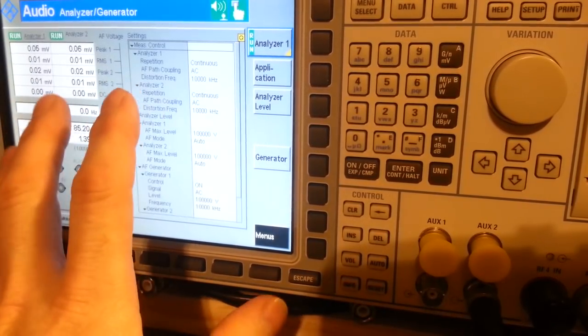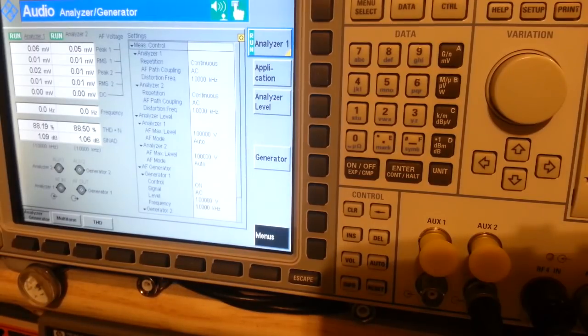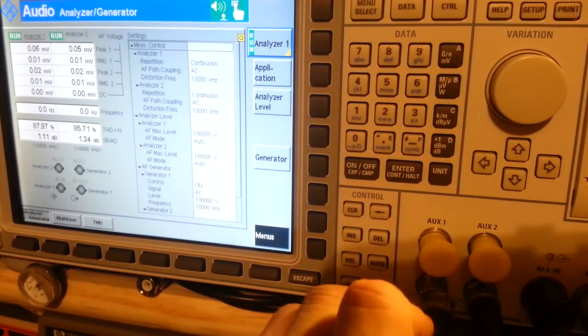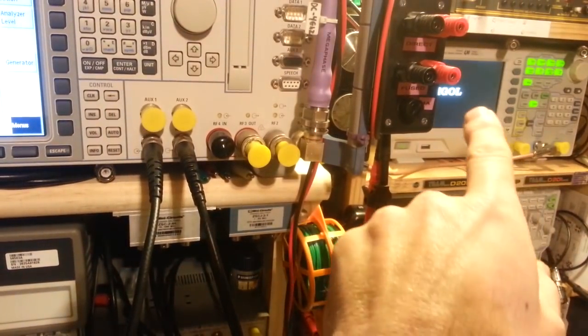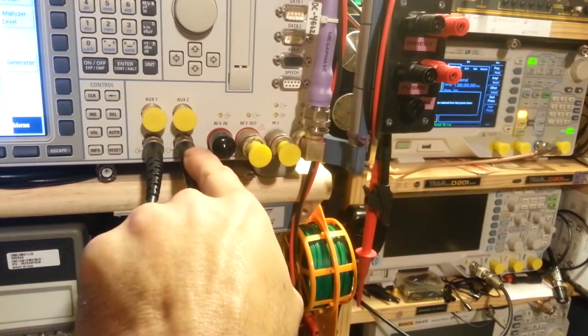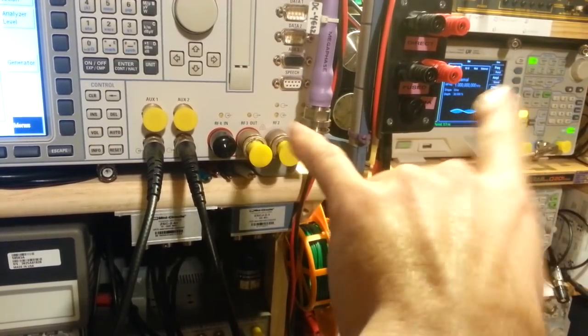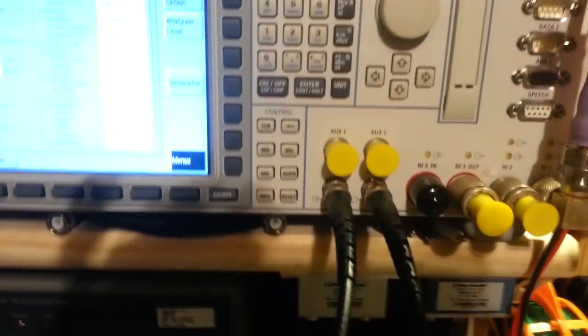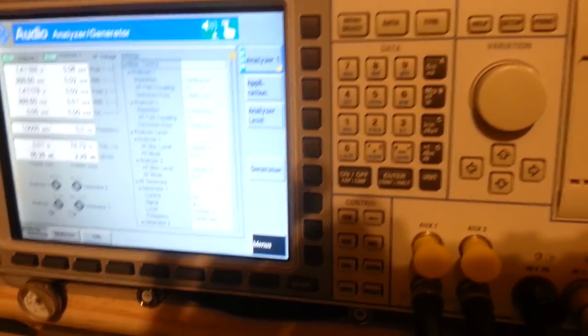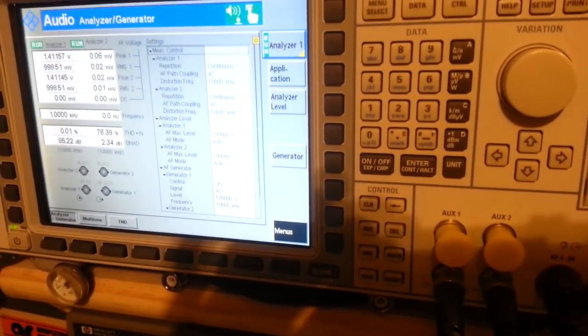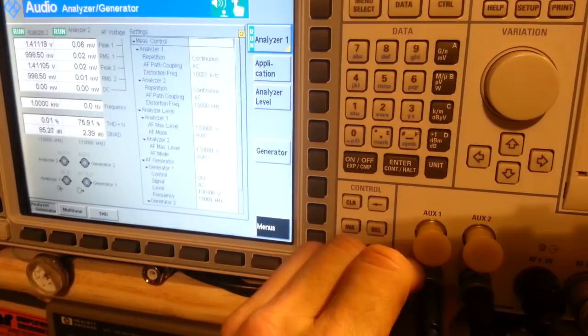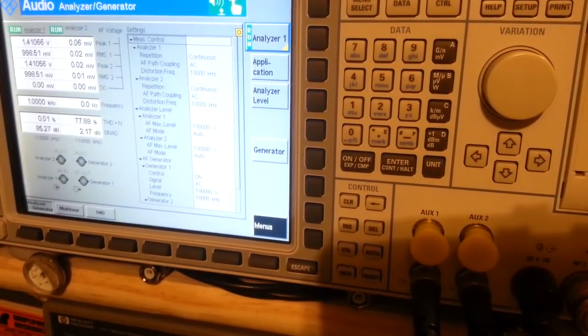And that's another thing I like about these. These communications test sets have precision audio signal generators. They're called low noise. And I can even demonstrate that if I turn on another signal generator. I'm going to fire up the Rigol signal generator over there. We'll take some measurements of the signal coming out of this one, and then we'll measure the audio signal coming out of that signal generator, and you'll be able to see that the audio in this one is more pure than that one. We can actually measure that with instrumentation here and show that the Rohde and Schwarz, being a much more expensive instrument, you would hope it would be a better signal generator, but we can actually measure that.